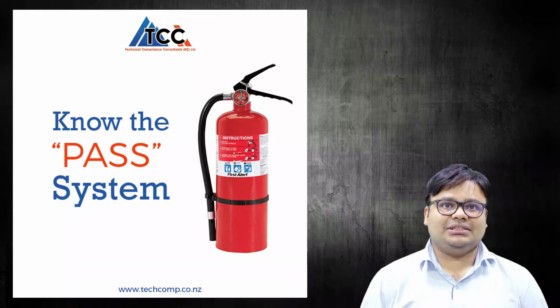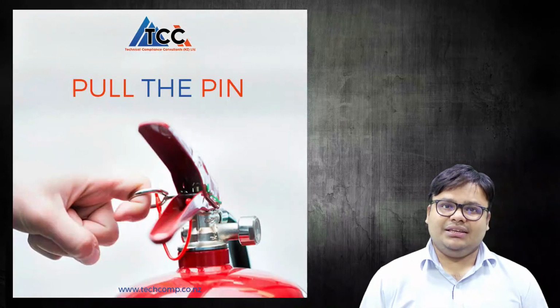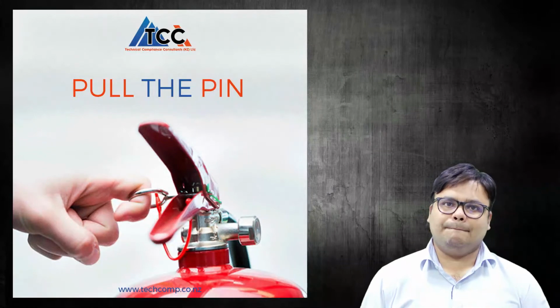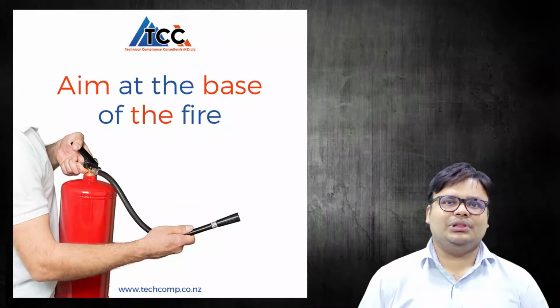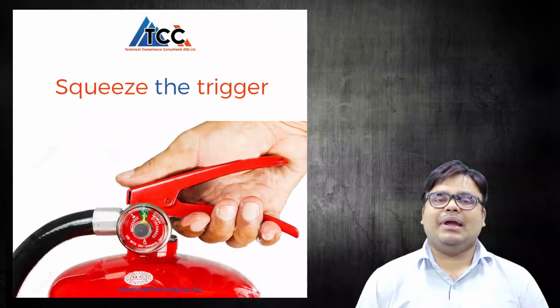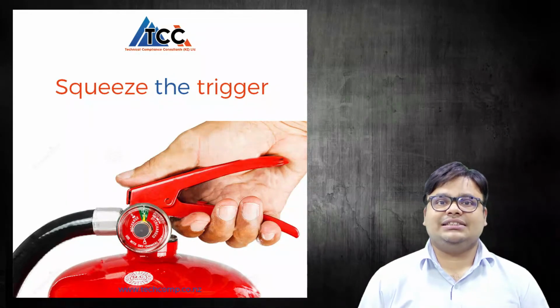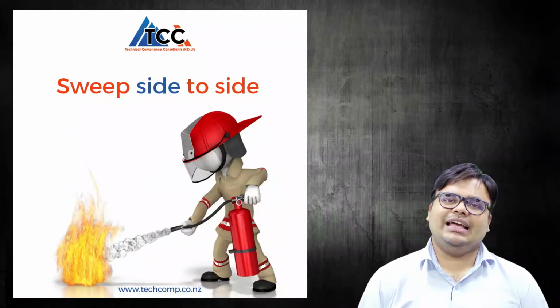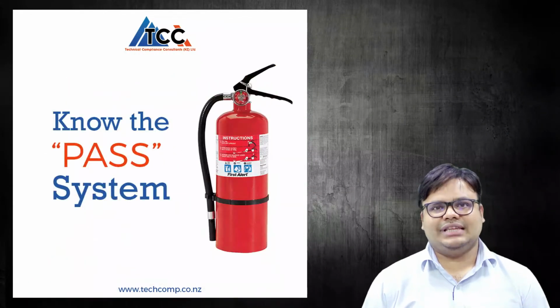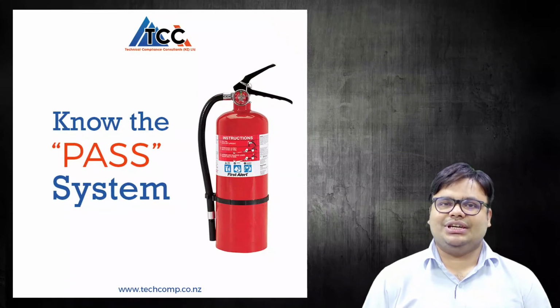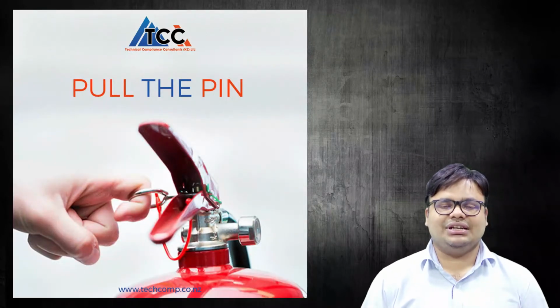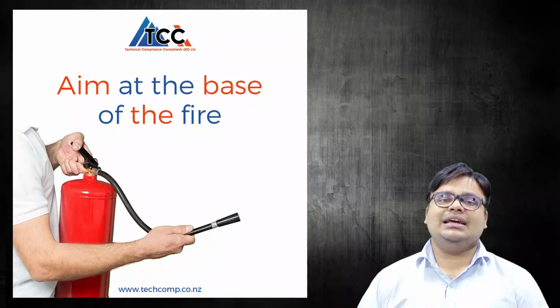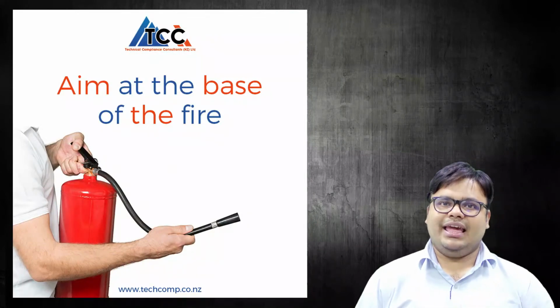Now as you can see, the P stands for pull the pin. So first we have to pull the pin, then A is for aim at the base of the fire, then S is squeeze the trigger, then the other S is sweep side to side. So this is the operating procedure of any kind of fire extinguisher. As you can see in the slide, its short form is PASS.